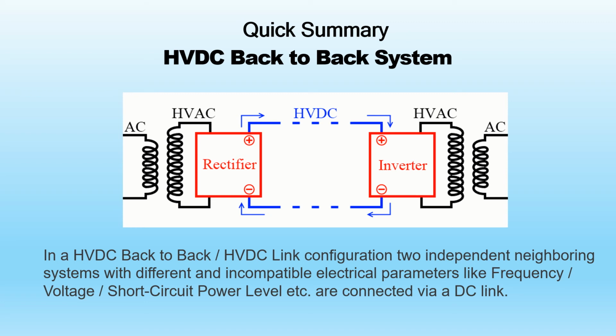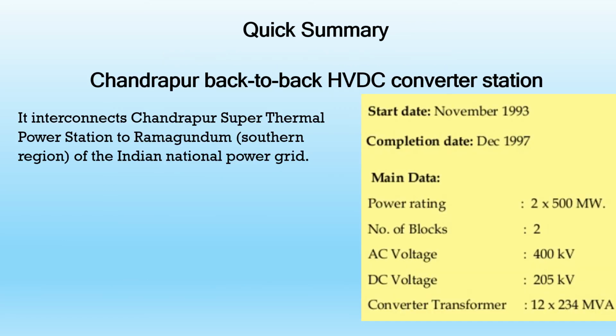Now let's look at a quick summary of what we have discussed till now. First we saw the HVDC back-to-back station, what it actually is. In an HVDC configuration, two independent neighboring systems with different and incompatible electrical parameters like frequency and voltage are connected via a DC link, as you can see in the picture. Then we saw the Chandrapur back-to-back HVDC converter station, which interconnects Chandrapur super thermal power station to Ramagundam in the southern region of the Indian national power grid.